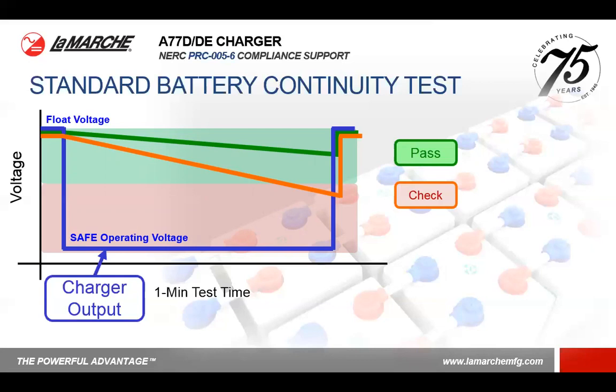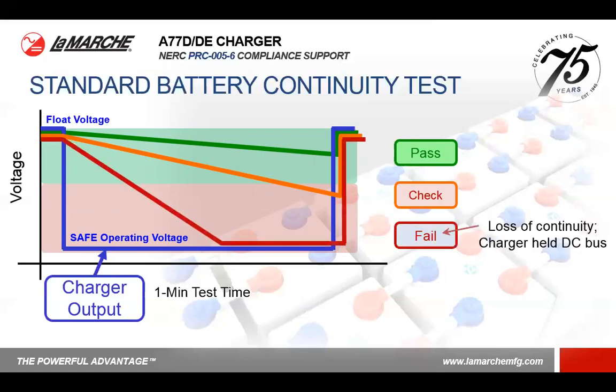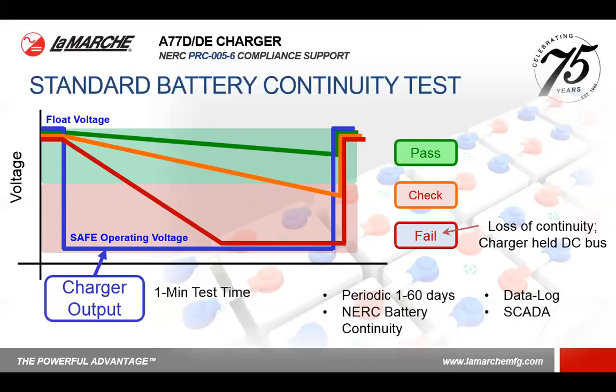This could be something as simple as a loose connection. This could be a loss of electrolyte. This could be an undercharged battery. There's a lot of things this could be, but we'll identify it for you. Now, on the off chance that the battery loses continuity, as in this last example, the battery voltage drops relatively quick, but it hits an asymptote at the safe operating voltage of the charger. And because this open battery scenario wasn't allowed to fall to 0 volts during the test, the charger kept the system up and running. Well, that's important, that the charger prevented a drop of the station load.